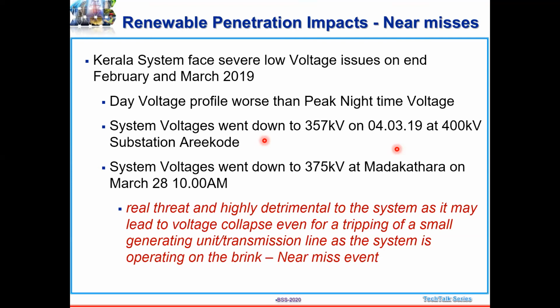And because of the irrigation loads, the motor starting, and the lack of inertia, the lack of conventional generation in the system, the fault level was very low and the voltage regulation became very poor. So there was huge fluctuation in the voltages. When all the irrigation pumps came into the picture, there was huge fluctuation in the voltage. The day voltage profile became very, very bad, and system voltage went down to 357 kV. See, 380 kV was the minimum, and it went down to 357 kV. The system was on the brink of collapse because of that problem in Kerala.